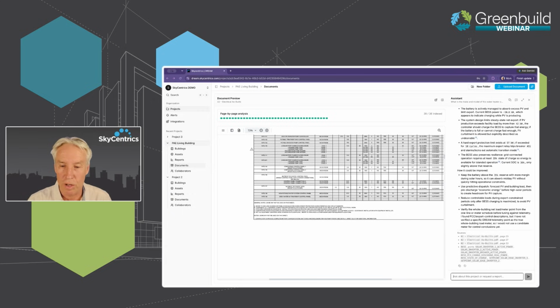Keep the battery above the 35% reserve with more margin, so during solar hours it can absorb the midday PV without quickly hitting operational constraints. Use predictive dispatch: forecast the PV and building load, then pre-discharge economic energy before high solar periods to create headroom for PV capture.